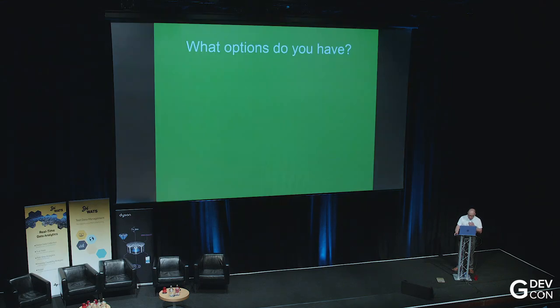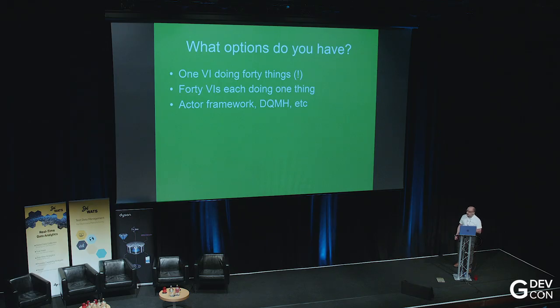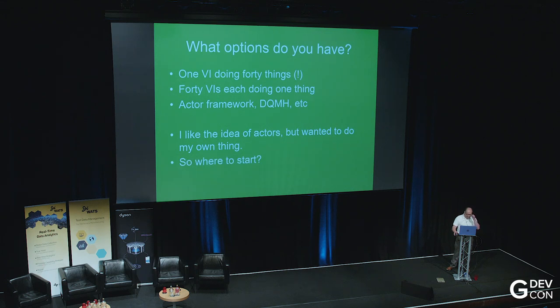So, it comprises multiple independent blocks. Some are one per system. So, there's a motor controller to move the tea bags. There's a spool motor controller to keep the tension in the tea bags correct. You've got some data logging. You've got a reed switch monitor. That's one per system. You've also got four modules, which each comprise a chemical balance monitor, a heater-chiller controller, a chemical pump controller, a temperature monitor, an ultrasound controller. So, in total, you're talking about 40 total actors. 40 independent systems that need to work together and that you need to control.